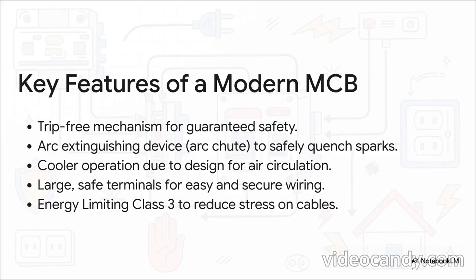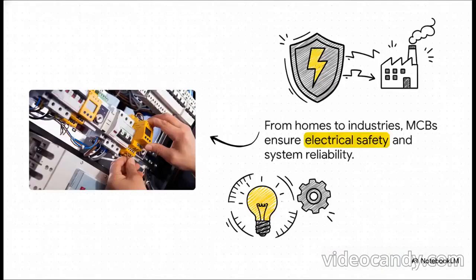And today's MCBs are just packed with cool features. For instance, they have something called an arc chute. It's basically a little chamber with metal plates inside designed to safely extinguish the dangerous electrical spark, or arc, that forms when you break a high-power circuit. They're designed with little grooves for better air circulation to stay cool. And they have a high energy limiting class, which is just a technical way of saying they trip so incredibly fast that they stop the destructive energy before it has time to damage the wiring in your walls.